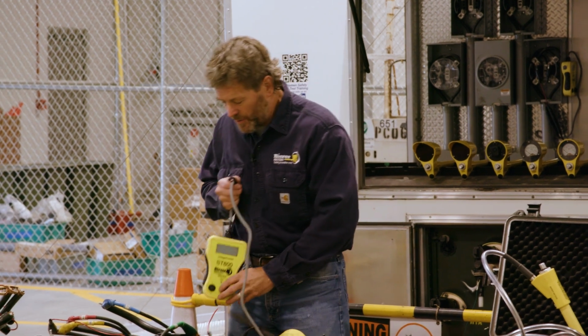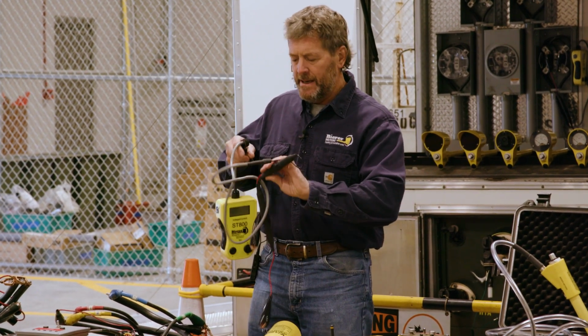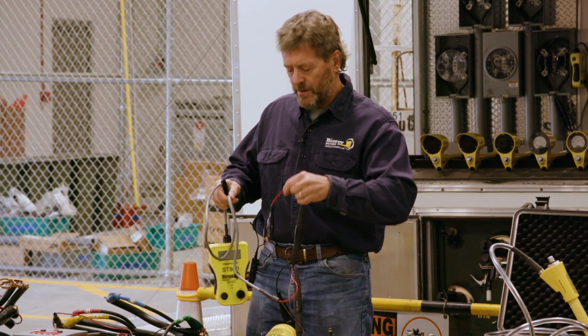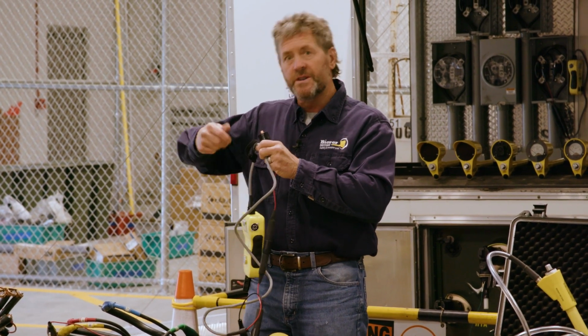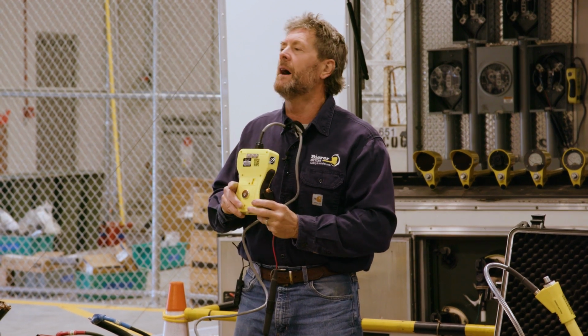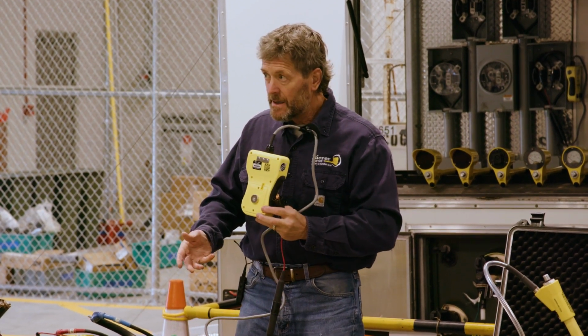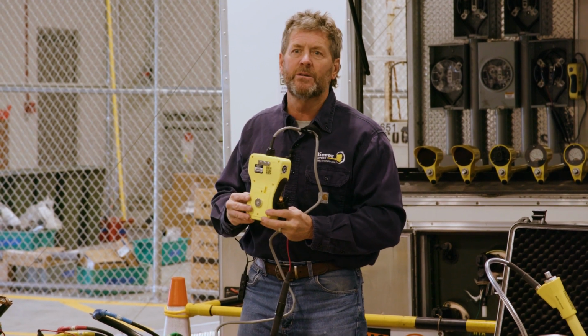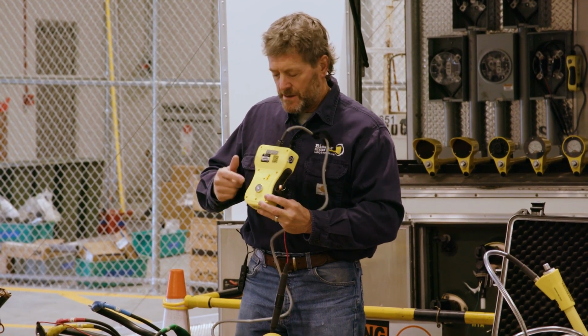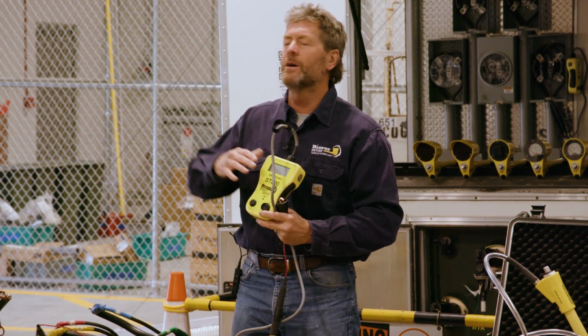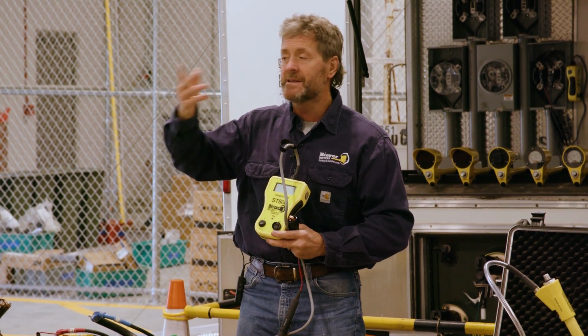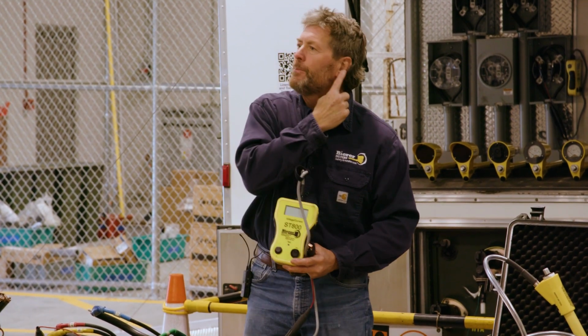So what we're going to do is continue the testing. We're going to find out which leg it is. We don't know yet. Hot leg 1 or neutral, we don't know. So what you're going to do is turn the tool off. You're going to take your red lead, and you're going to go to hot leg 2. Turn the tool back on, look at the voltage. Well, we're seeing 100 volts. Again, so now the common denominator is you got a neutral issue. Turn it on, go up to the load, and you expect to see slow counts. And you expect, because it's the same situation, that it's going to get up to about 40 amps, fall on its face, recount, you're going to hear popping.